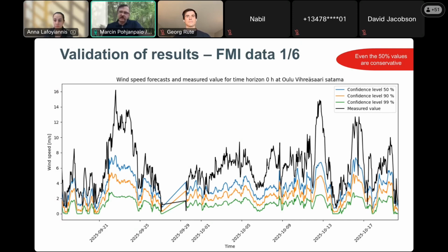Yes, the goal is that we want to use DLR in pretty much everything where it's needed. Currently we have a real-time process running every 30 minutes to check if we have any issues on the grid, and that's already partially fed by this. As we take more lines into production, it'll have more DLR lines in that system. I just see this as the new normal, that all the systems running in real time will have real-time data. For economic dispatch and unit commitment, it's not really my field, but since the data will be available company-wide, I don't see any problems with anyone who has the need just grabbing it.